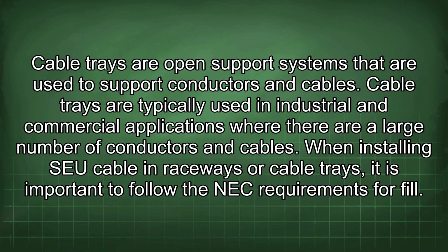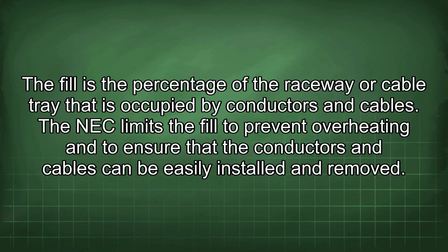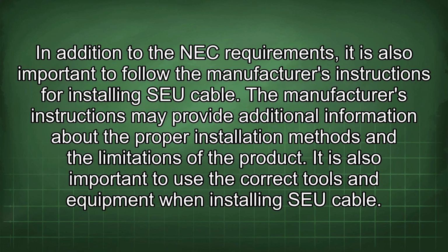When installing SEU cable in raceways or cable trays, it is important to follow the NEC requirements for fill. The fill is the percentage of the raceway or cable tray that is occupied by conductors and cables. The NEC limits the fill to prevent overheating and to ensure that the conductors and cables can be easily installed and removed. In addition to the NEC requirements, it is also important to follow the manufacturer's instructions for installing SEU cable. The manufacturer's instructions may provide additional information about the proper installation methods and the limitations of the product.